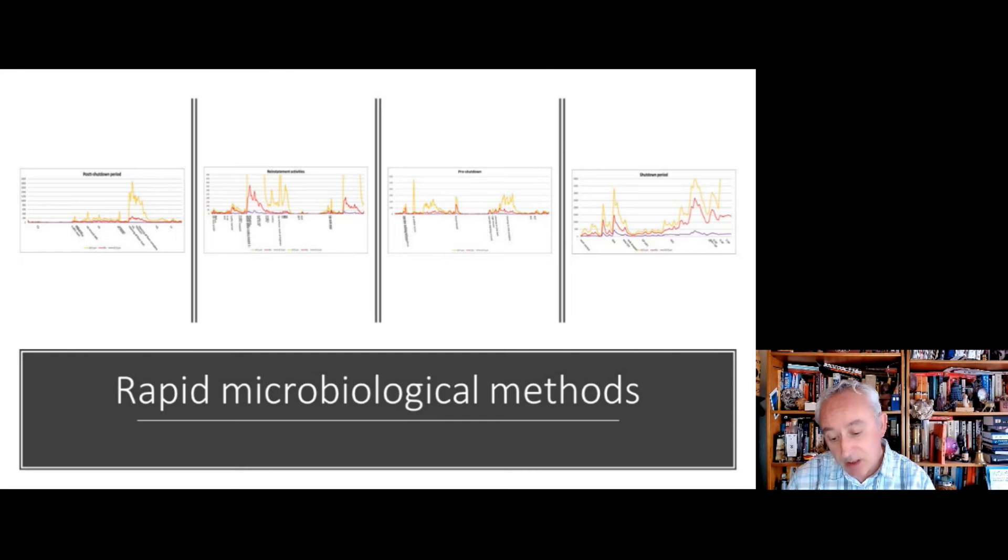And this gives us an understanding of what type of events trigger the highest biological readings and how long the clean room is required to rest. We can get an understanding of what's normal in terms of biological activity, the impact of people in the area, equipment movements, and so on. What happens when we declassify areas, the impact of cleaning, and then this whole recovery period and time.